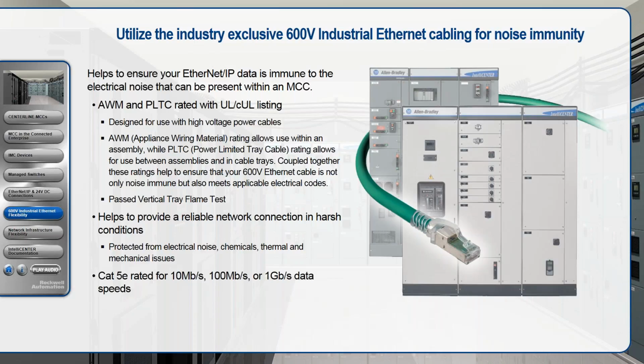I mentioned that our cabling is 600 volt rated. We go through extensive fast transient burst immunity and electromagnetic conformance testing on all of our products, as well as in line with our communication networks, because we want to provide a reliable network connection. Our 600 volt rated cabling is designed to be used alongside those higher voltage power cables that could be coming in those top or bottom wireways, or alongside your MCC too.